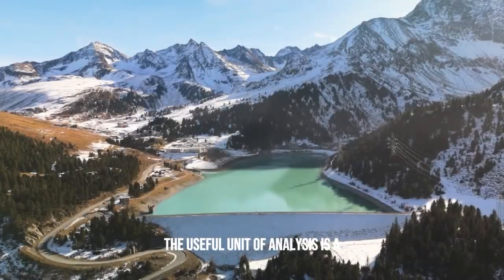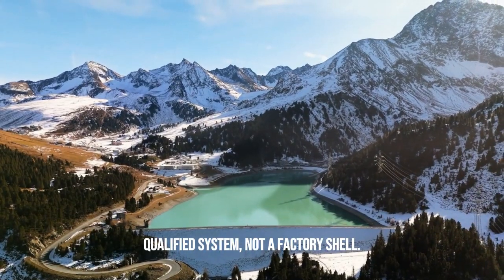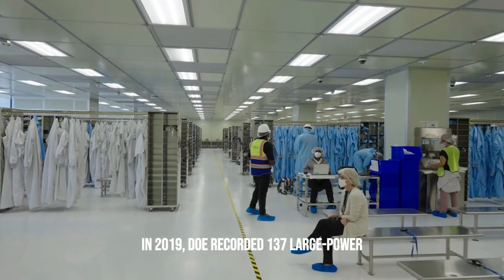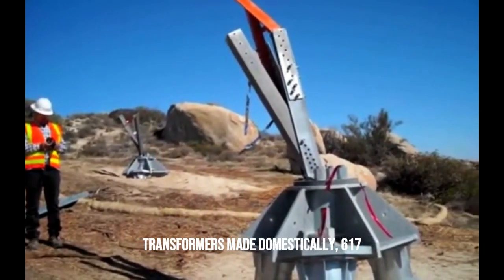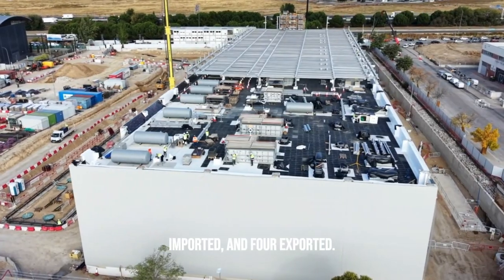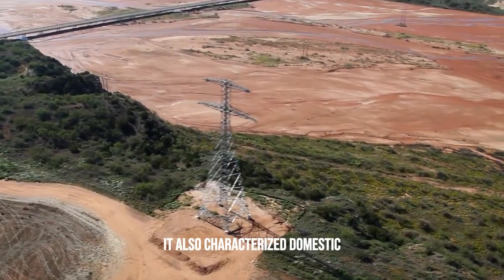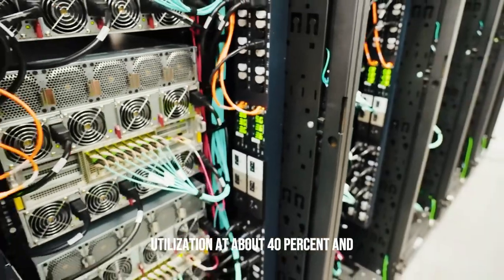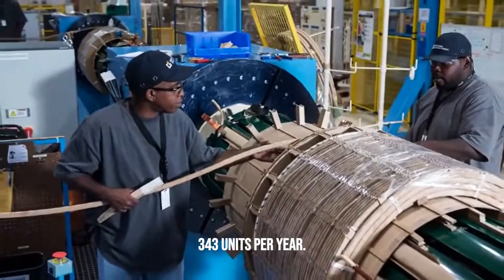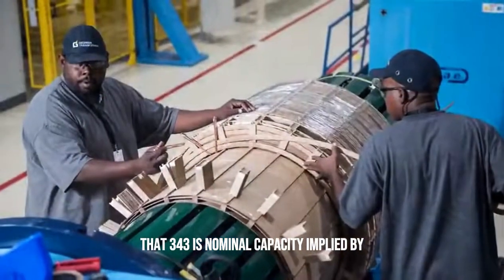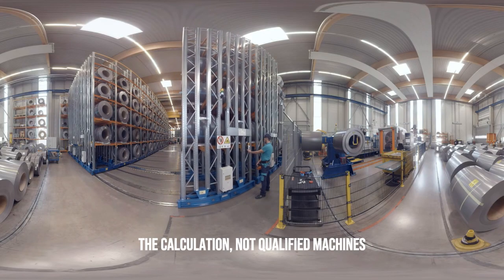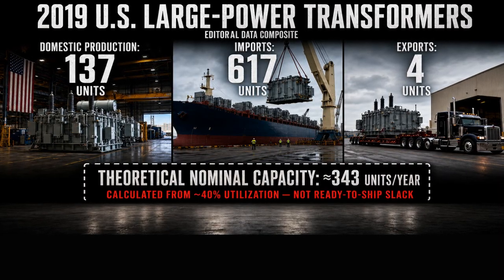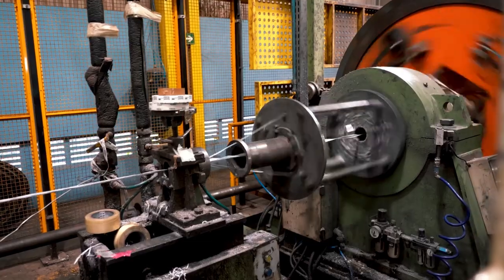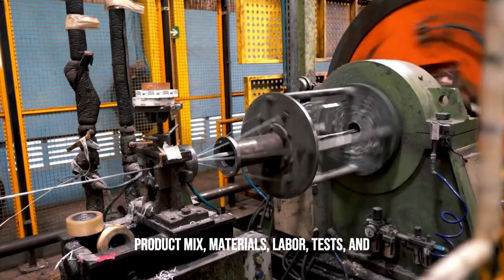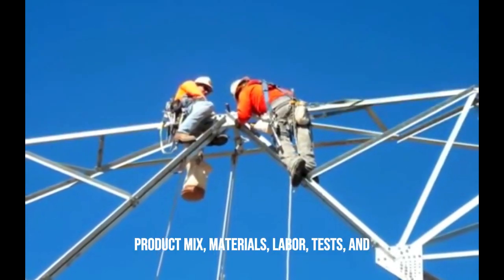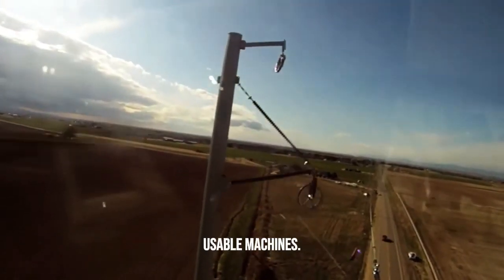The useful unit of analysis is a qualified system, not a factory shell. In 2019, DOE recorded 137 large power transformers made domestically, 617 imported, and 4 exported. It also characterized domestic utilization at about 40% and derived a theoretical maximum of about 343 units per year. That 343 is nominal capacity implied by the calculation, not qualified machines ready to ship. The 617 imports are a separate count, not domestic slack. Product mix, materials, labor, tests, and specifications decide which slots become usable machines.